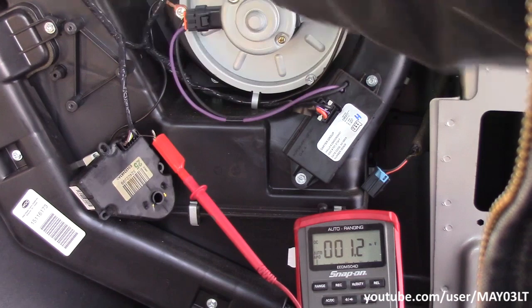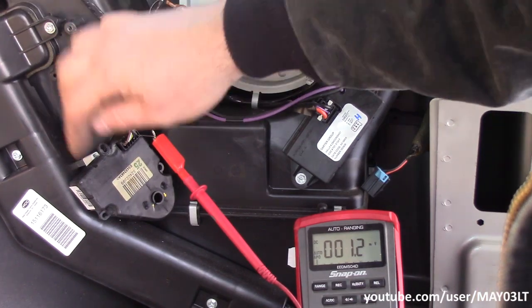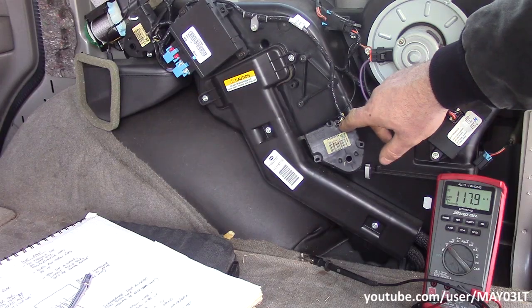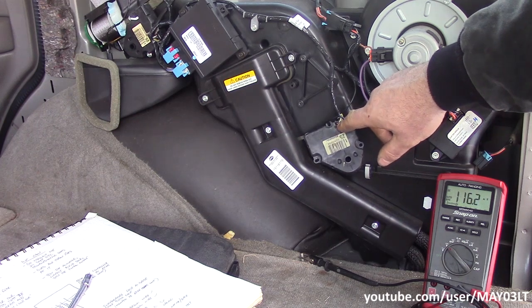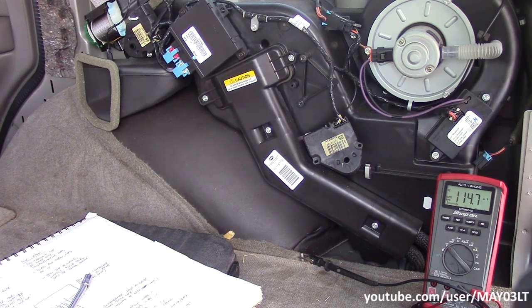The problem might be with the module itself not supplying the right signal to move the motor. I want to see what happens on the control circuit - I want to see if we get a voltage on the white and black wire that changes depending on where we turn the temperature.